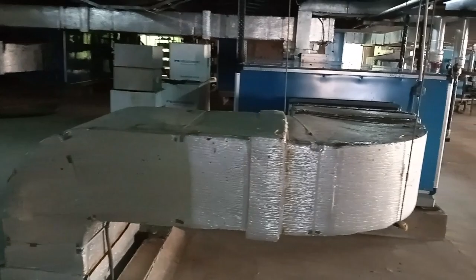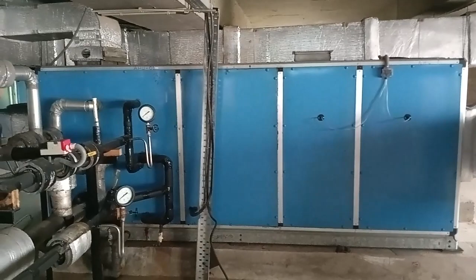These are called AHU, air handling units. There are 9 air handling units for this infrastructure, and the input of each is first the air and then the chilled water. On the other side, we have 3 chillers where the temperature is maintained around 18 degrees centigrade. Sometimes it may need to be 12 degrees also. Those chilled waters come up to the grid within the chamber. It's a copper grid. The chilled water passes through the grid, and the air coming from the chase area and from the fresh atmosphere will cross those copper grids. As the temperature of the grid is around 12 to 18 degrees centigrade, the air will condense.